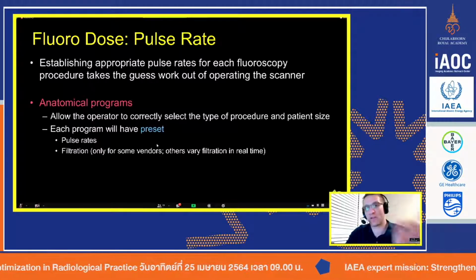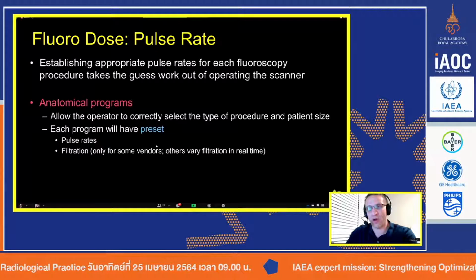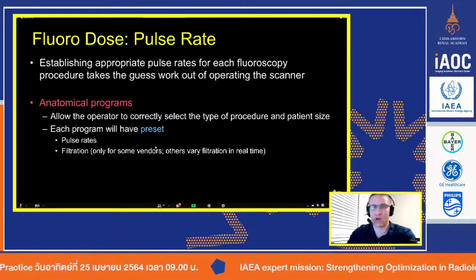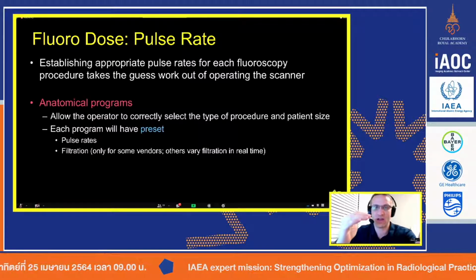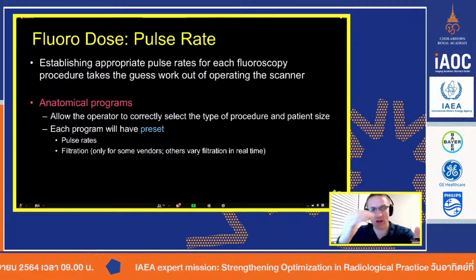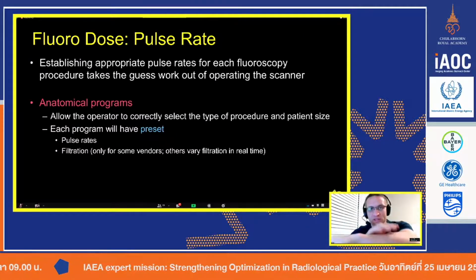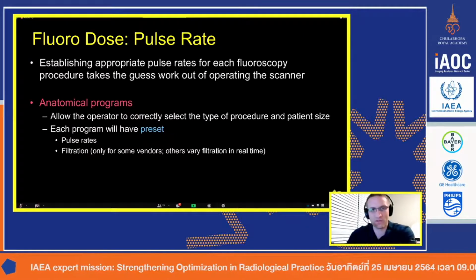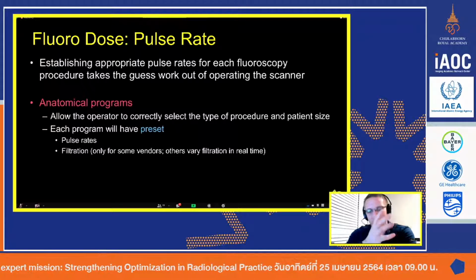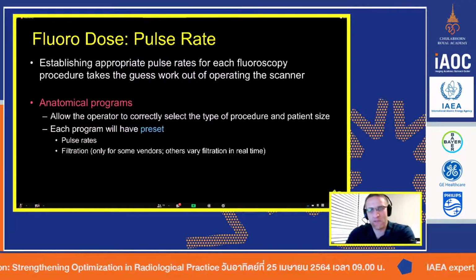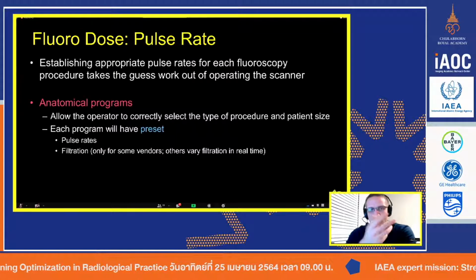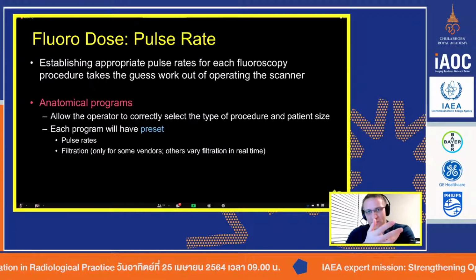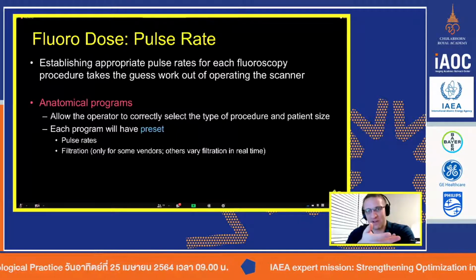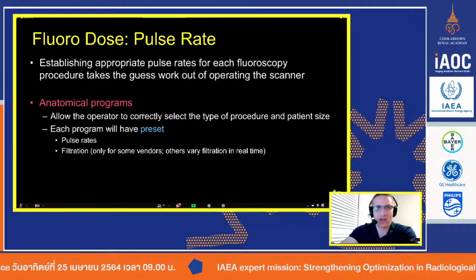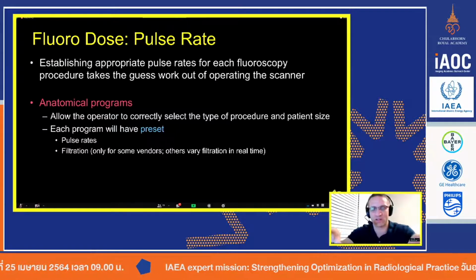We talked about this last week, how all of the systems tend to want to use the highest filtration possible. The higher the filtration, the lower the skin dose. That's the whole reason we use filtration in fluoroscopy. Well, 90% of the reason. The other 10% is to improve the image quality, to improve contrast. Too much filtration, however, can adversely affect contrast because your kV goes up. Higher kV means lower contrast in the body.